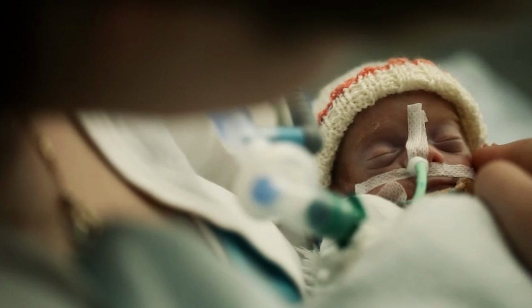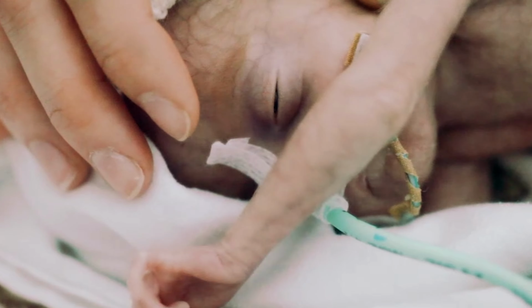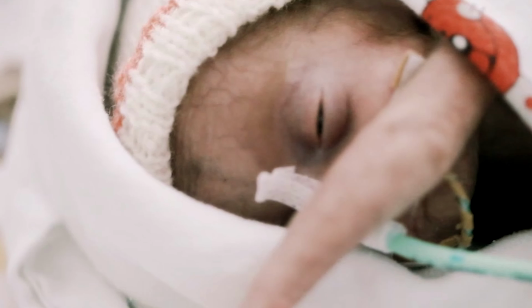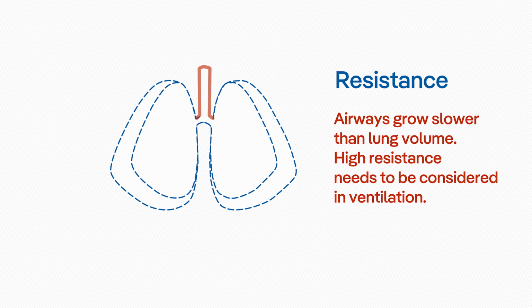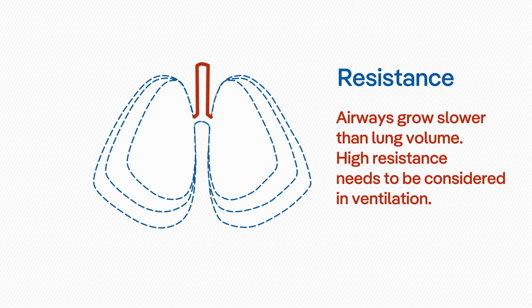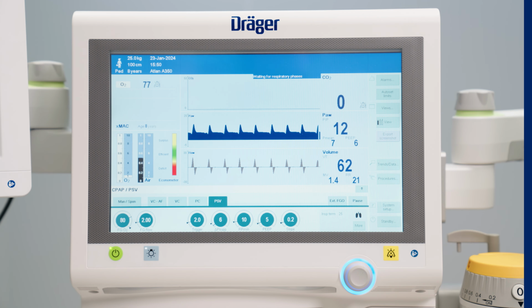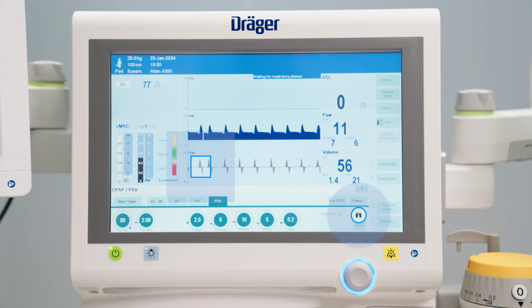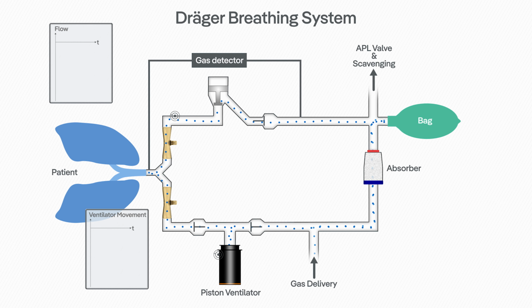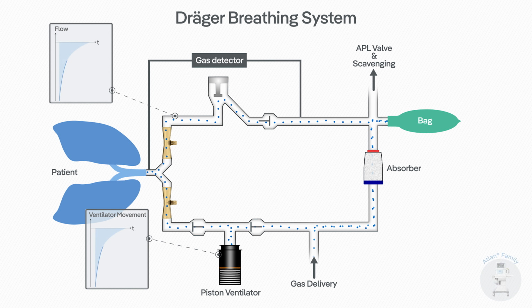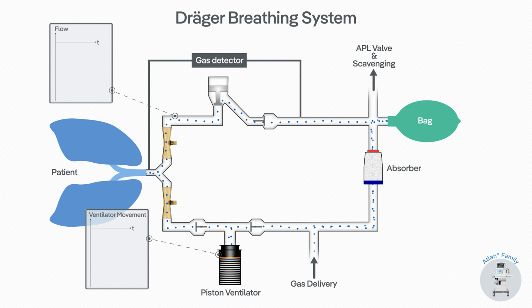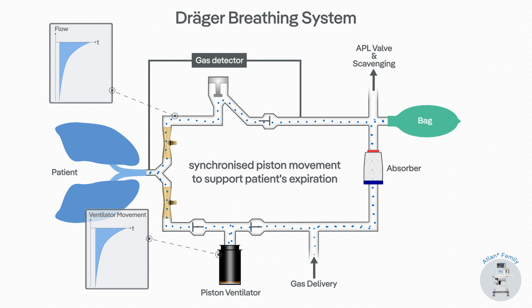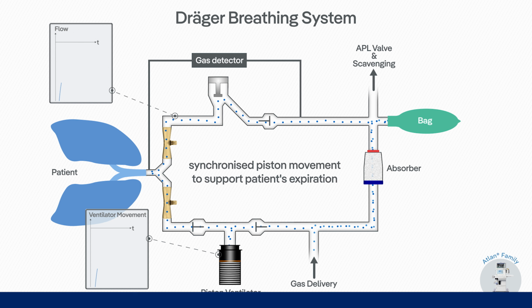In ventilation of small children, it is vital that the system detects the smallest effort of a spontaneously breathing patient to provide support when it is needed. Also, the breathing system resistance should be as low as possible to reduce the work of breathing. Dräger anesthesia devices provide highly sensitive flow triggers, so that even the weakest spontaneous breathing attempts are reliably detected. The E-Vent Plus piston ventilator in Atlan family devices regulates its movement during expiration to synchronize with the expiration flow and so actively supports the patient's expiration.